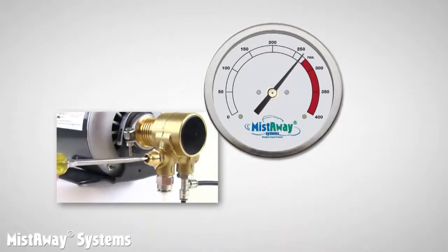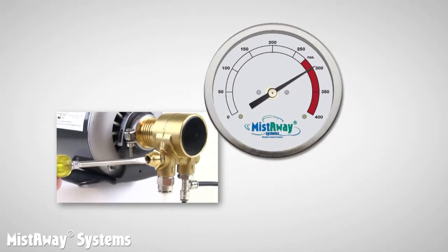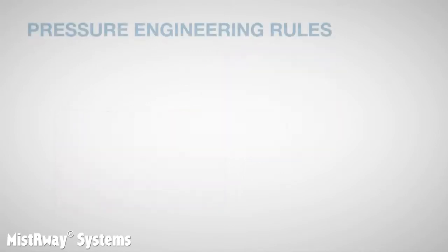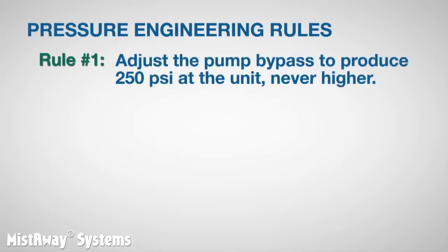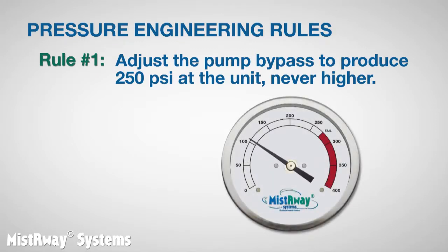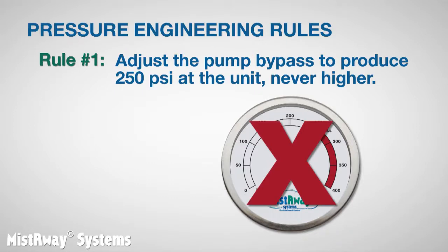It is very important that you understand the limits of the pump when adjusting the bypass. The pumps will fail at sustained use above 275 psi. Which brings us to rule number one. Adjust the pump bypass to produce 250 psi at the unit, never higher. If your pump is set at 250 psi and you are having problems getting adequate pressure and flow out of your nozzle circuit, don't increase the pump pressure to fix the problem. The problem is not the pump.